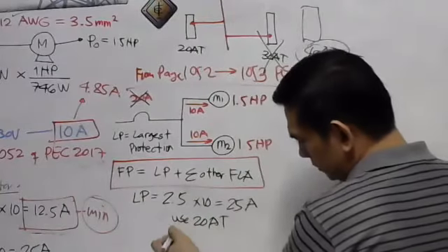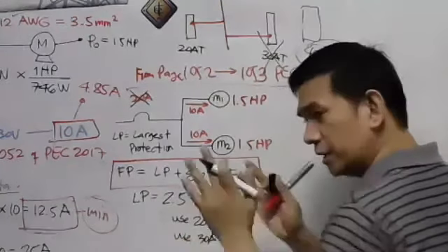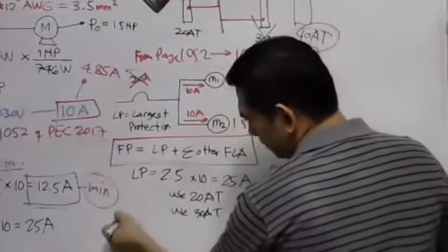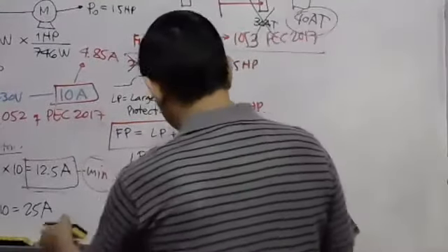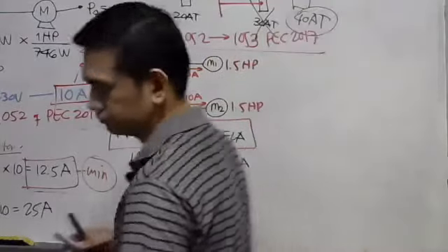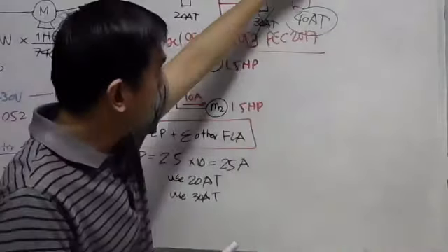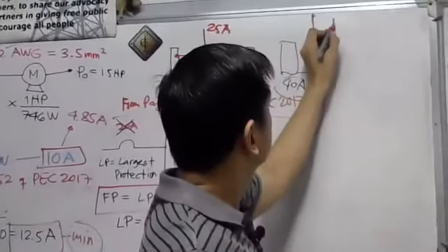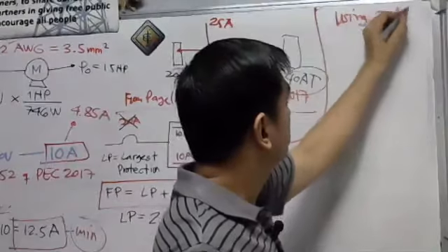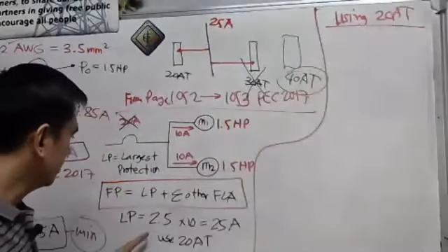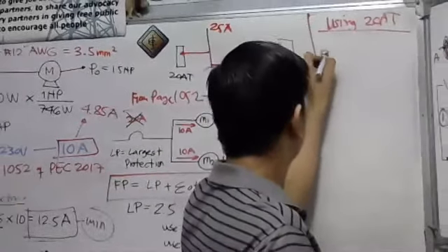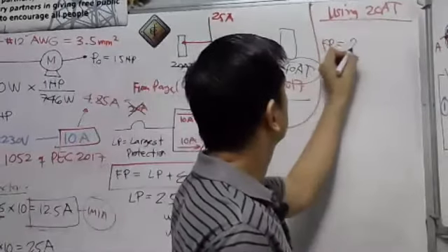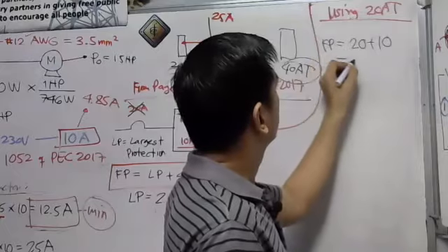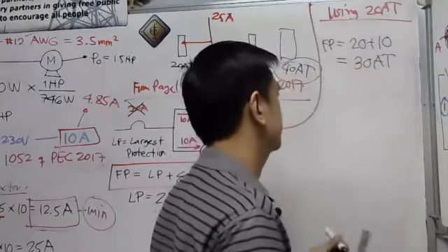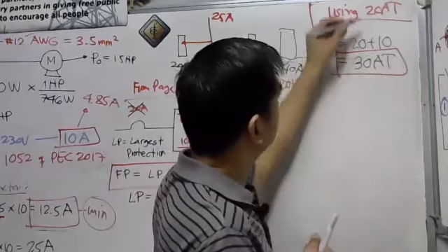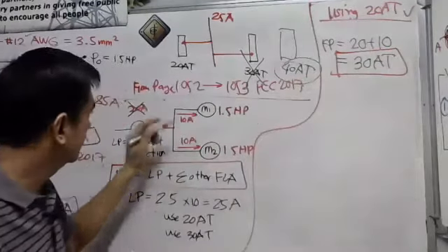Well, many professors will use 30 ampere trip. I'll show you the two points of view here. For the feeder protection, let's say using the 20 ampere trip for each motor. Let's say using the 20 ampere trip circuit breaker. If we use the 20 ampere, what is the size of the feeder protection? The feeder protection will be 20 plus 10. So the answer is 30 ampere trip. So that is one size because we use the 20 ampere trip for a single motor. Of course, there is a circuit breaker here.